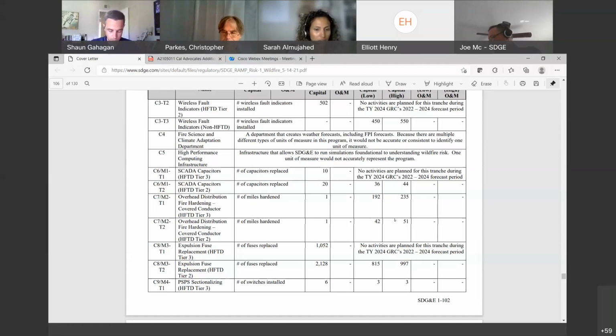We don't have things to report on just yet, but we're learning as we go from the pilot, and we see a lot of potential in it. The bare conductor hardening we've done has given us about a 47% reduction in ignition rates compared to the past, and we think covered conductor could come close to that, adding value by reducing the potential for foreign object contact starting ignitions.